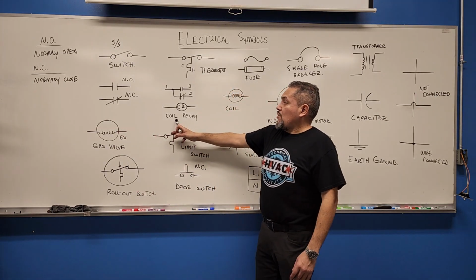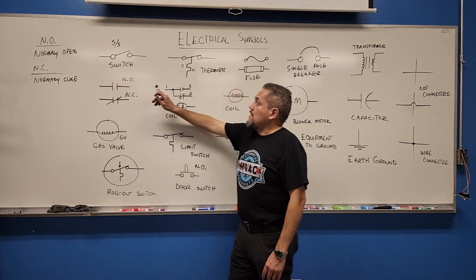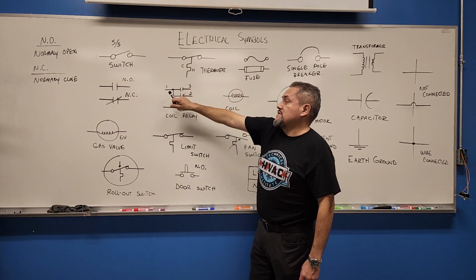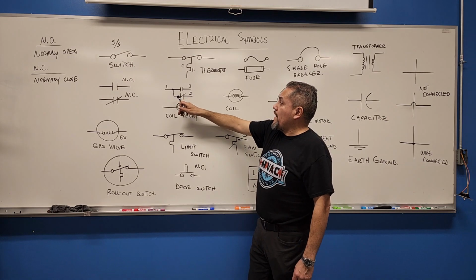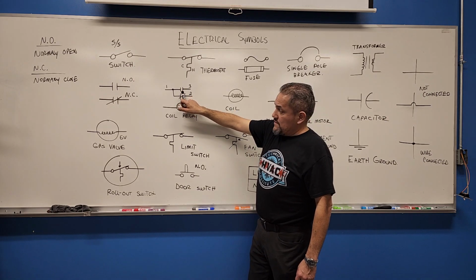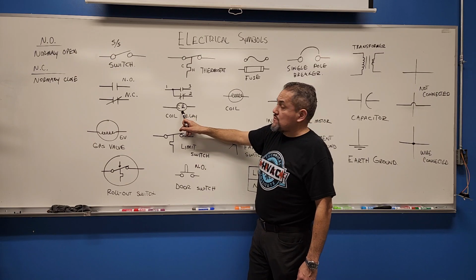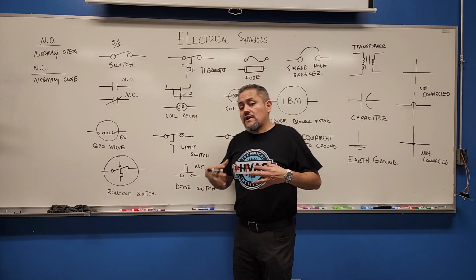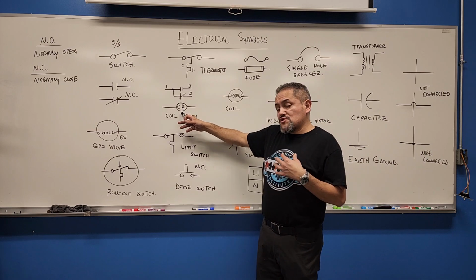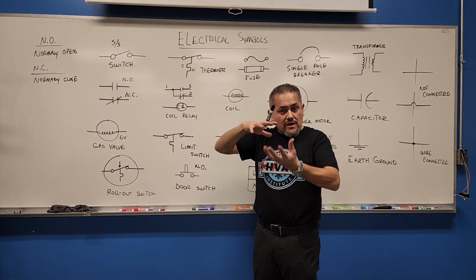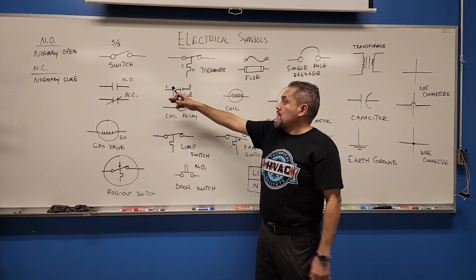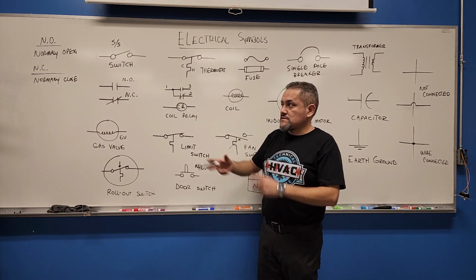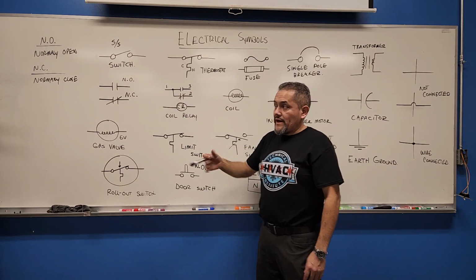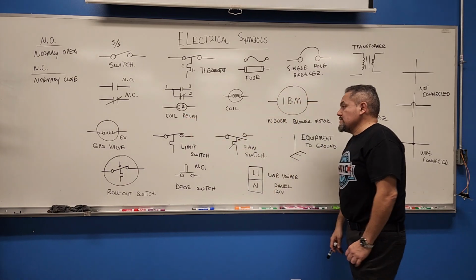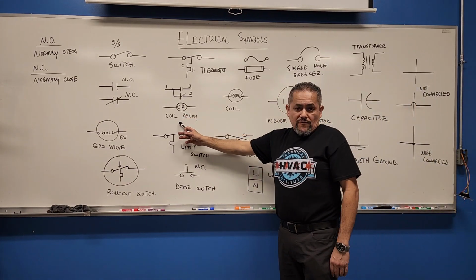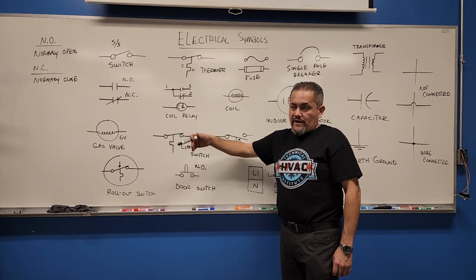The next symbol is the coil relay. Coil relay is similar to this. Number 1, voltage comes in. Number 2, normally closed to 1. Number 3, normally open. And this is the coil relay. You need to send 24 volts to the coil relay so the relay can actually switch the contacts. 1 to 3 close and 1 to 2 open. So it pretty much does the opposite as you energize the coil relay. Okay, we're going to talk about this. This is for the evaporator fan motor when you call for fan on.